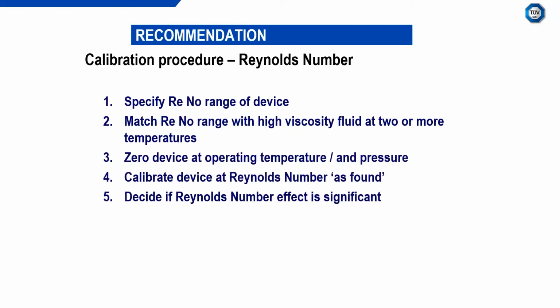That aspect ratio appears to be significant. It's definitely true that not all Coriolis flow meters have a significant Reynolds number effect. It appears to come back to, as I say, that aspect ratio. Certain devices are affected, others aren't. So we'll decide if the effect is significant, and then we can perform an as-left calibration if required.